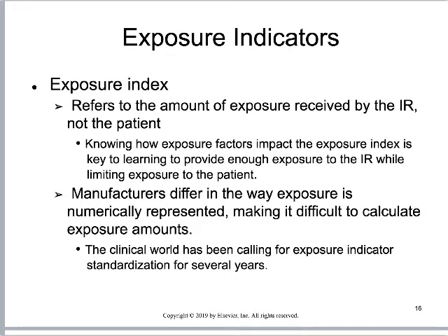Changing gears, one significant technical consideration with digital images is that we cannot look at the image and determine whether the exposure was appropriate. We need to rely on the computer to tell us what the exposure level was — that's what we mean by exposure indicators. Exposure indexes are the amounts of exposure received by the image receptor, not necessarily to the patient. It's the latent beam exiting the patient and exposing the image receptor. Knowing how these exposure factors work is key to providing sufficient exposure to create a diagnostic image.